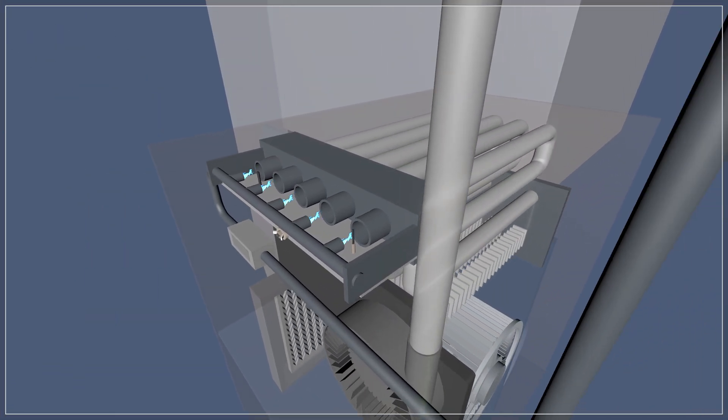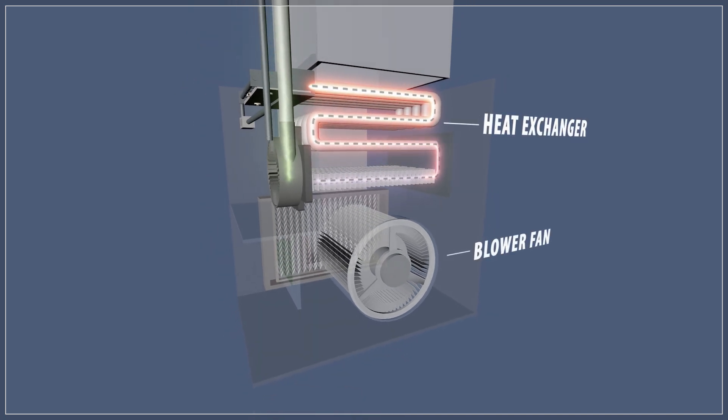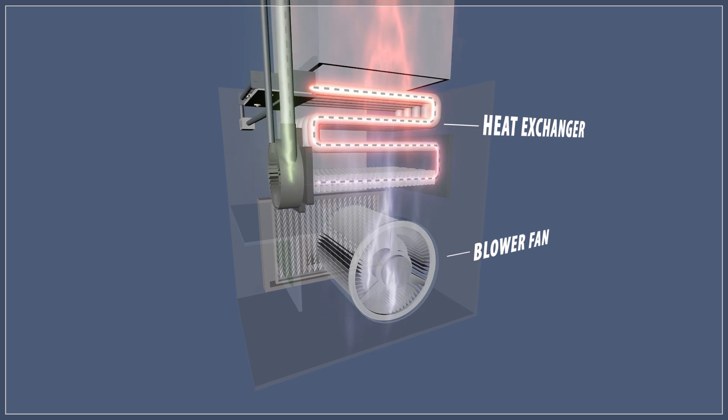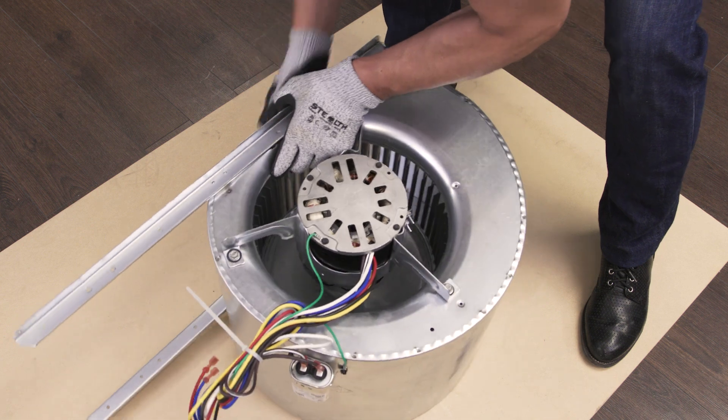When the burner is lit, the blower fan is delayed from running to allow the heat exchanger to warm up. This prevents the furnace from circulating cold air. If the blower still doesn't run after a minute or two, then the motor might be seized or burnt out.